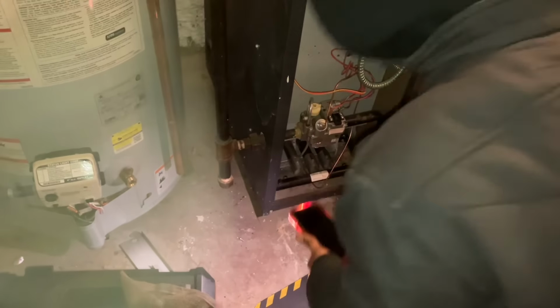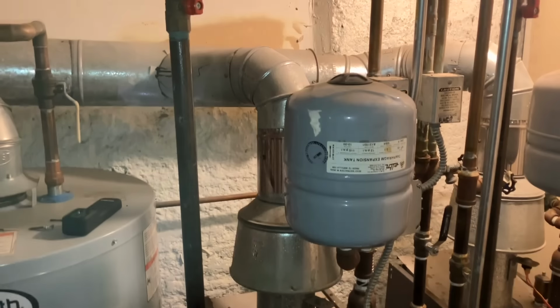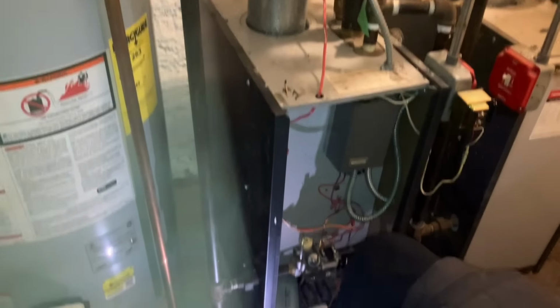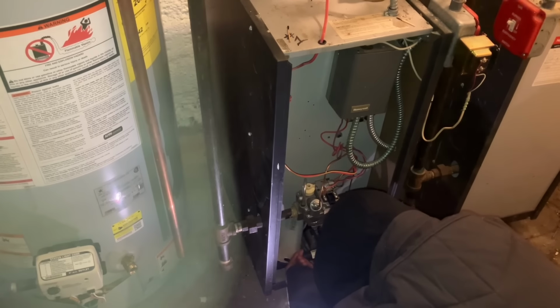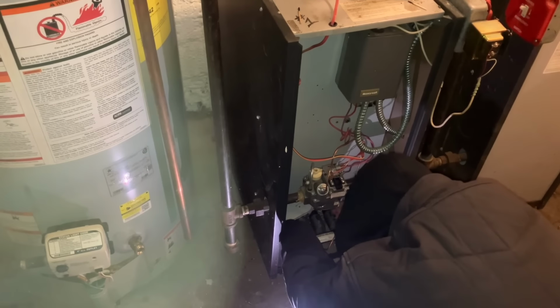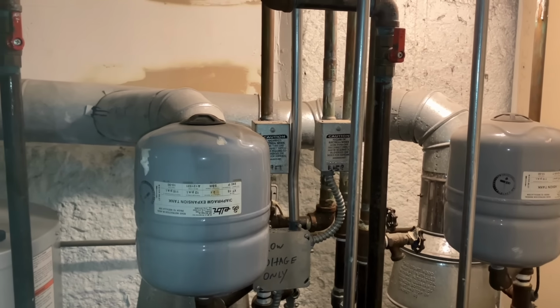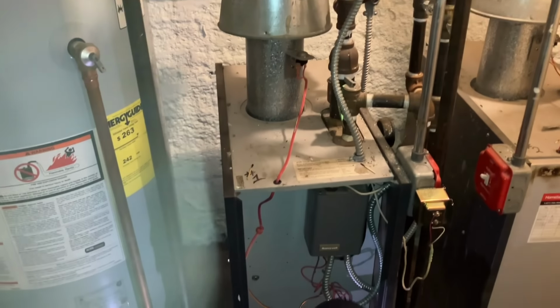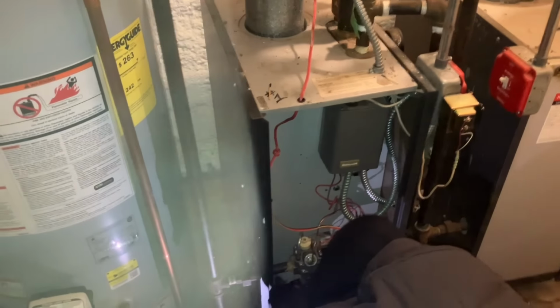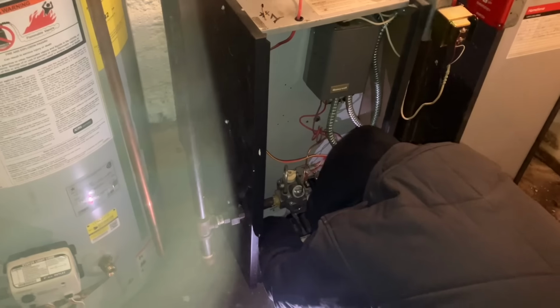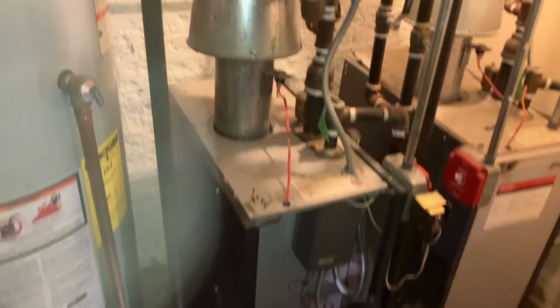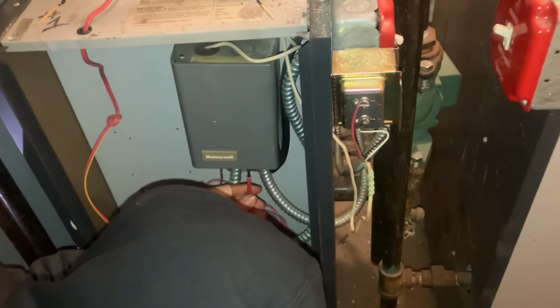Put the front combustion plate back on, do a little vacuum and cleaning of everything and the exterior. Then we'll check our temperature and pressure, the relief and the expansion, zone valve operation. Wipe everything down with a nice oiled rag. Make this bad boy shine. Beautiful. All right, let's see what this Aquastat is set to.